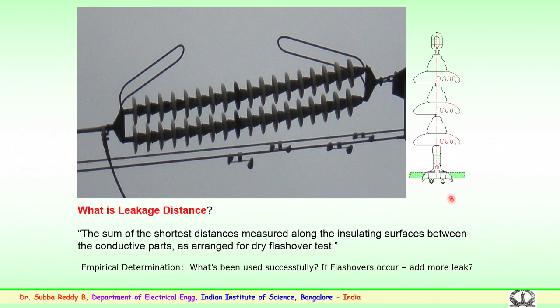So, now we have discussed the importance of insulation coordination, why insulation coordination has to be done for any equipment including the insulators. The second important criterion is how this insulator or insulator assembly, whether of pin type insulator or long rod insulators, helps in the field both mechanically and electrically in the transmission system. And we have also looked into the importance of the dry arcing distance and the difference with the leakage distance.